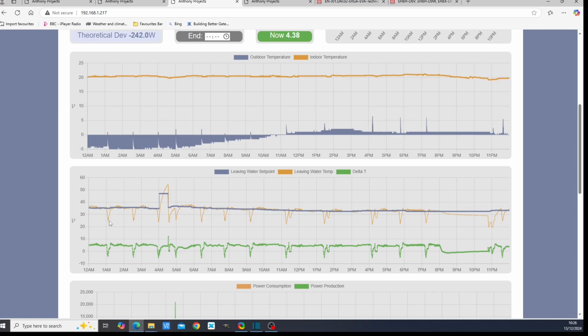And we had a couple of defrost cycles here. And there was about one and a half hours between the defrost cycles. Sometimes we can get some very frequent cycling going on, and a lot of it is down to the humidity of the air on that particular night. The more humid the air is, the more frequent the defrost cycles are going to be. But this is characteristic of your defrost cycle.